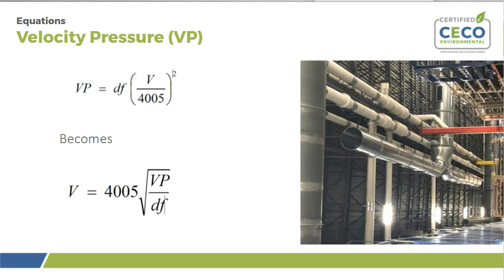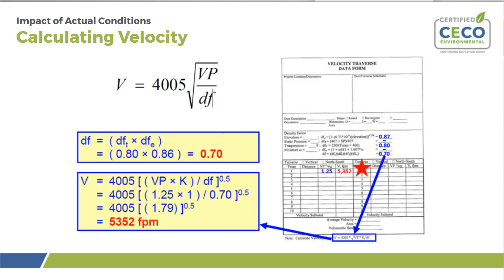However, if we have temperatures that are above standard, say 150 degrees Fahrenheit or greater, or elevations above 2,000 feet, it would be worthwhile to calculate the actual air density. The actual air density is a product of the density factor for temperature and the density factor for elevation. In the example above, we see that although each density factor itself, the one for temperature and the one for elevation, is not that significant, being 0.8 or greater, when we multiply them together, the overall density factor is 0.7, and that is significant in regards to being able to determine the actual flow. So if we do deviate from ambient conditions, it would pay to consider the density factor.